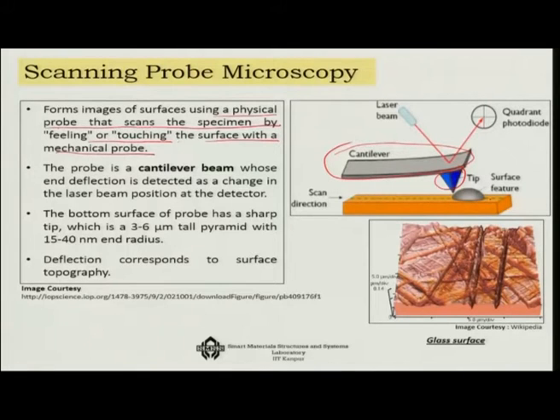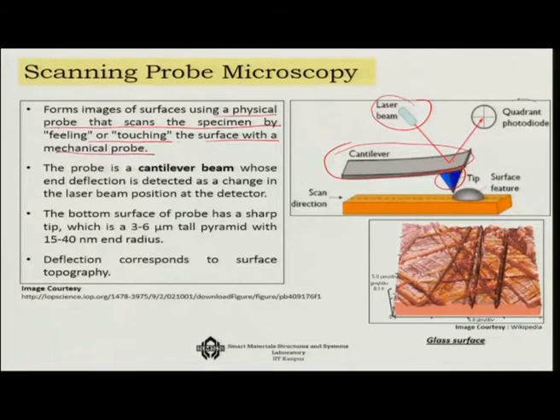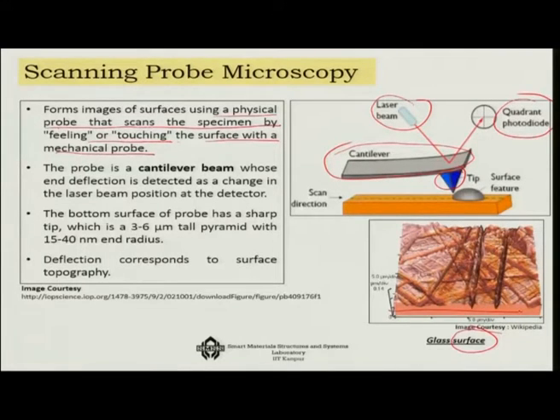The material has many kinds of undulations. The probe touches the surface and as it is touching, its deflection is changing, which is picked up by a laser beam. The light coming from the laser beam reaches a highly sensitive quadrant photo diode, and from the deflection it finds out the nature of the surface of the sample. The very important tool in scanning probe microscopy is the cantilever beam whose end deflection we detect as a change in laser beam position at the detector.